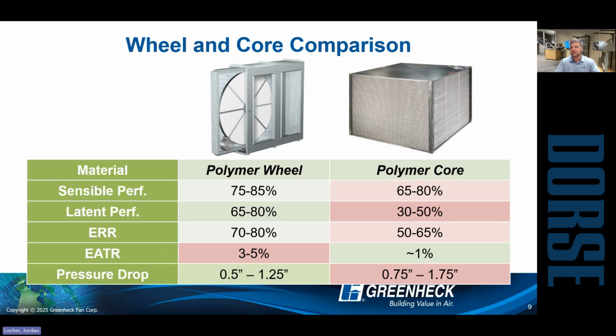However, I would say that code requirements state that you have to have less than 5% leakage to handle class 3 air, right? So if you're not familiar with what that is, class 2 air, that's like your bathroom exhaust, right? Typically to handle bathroom exhaust with an ERV or DOAS system, you have to be less than 10% leakage. And to handle class 3, so that's like a vet office or a nail salon, you have to be less than 5%, right? So that is one true advantage of a core.